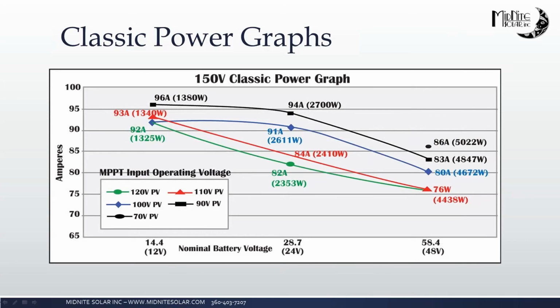If we go way back to that string sizing tool and that 1.2 Classics allowed because of the 80% nameplate, if you're doing a system where the controllers are going to run flat out all the time, similar to a battery-based grid tie, and it's a larger system, then we may not want to load them to 100%, just to keep the heat out of the electronics. And I'm not saying that as a MidNite employee. I'm saying that in general, with any electronics, if we can keep them 80% or below on their ratings, they're going to be so much cooler, they're going to be so much happier, and they're going to reward you with a very long life. So heat is always our enemy with electronics, so just remember that. Sorry for the tangent, but I just felt that fit in there somewhere.